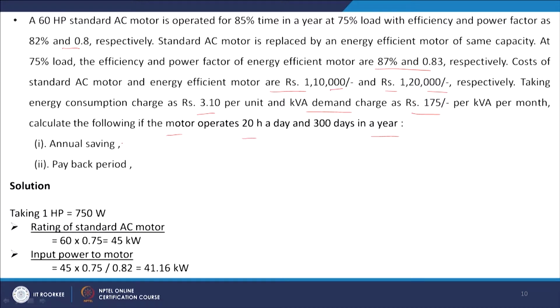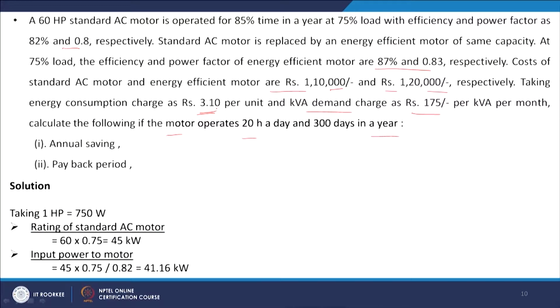So, we have to calculate annual saving and payback period. So, this is the problem statement. If we want to do it, then what we have to calculate? We have to calculate the energy requirement in case of the standard motor and the energy requirement in case of the energy efficient motor. In this case the energy efficient motor will be using less energy, and that amount of less energy is our saving. To get the monetary value we will multiply this by the unit price of the electricity, then that is the total monetary saving, and then we can calculate the annual saving, and we can get the payback period.